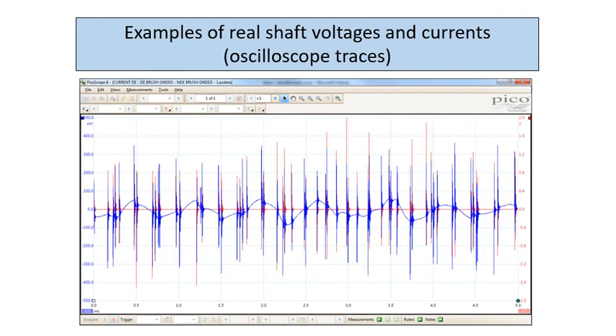Okay, onto the traces. This is the VSD installation. The voltage is blue and the current is red. The scales are here in red: 3.2 volts will be 3.2 amps. So you can see you've got up to 1.6 amps of shaft current. You can see the spikes go with the voltage, and then you can see there's a fairly sinusoidal component. You're talking about milliseconds, that's 2.5, and this goes with the drive switching frequency. Okay, that's on the drive end, with the drive end brush grounded.